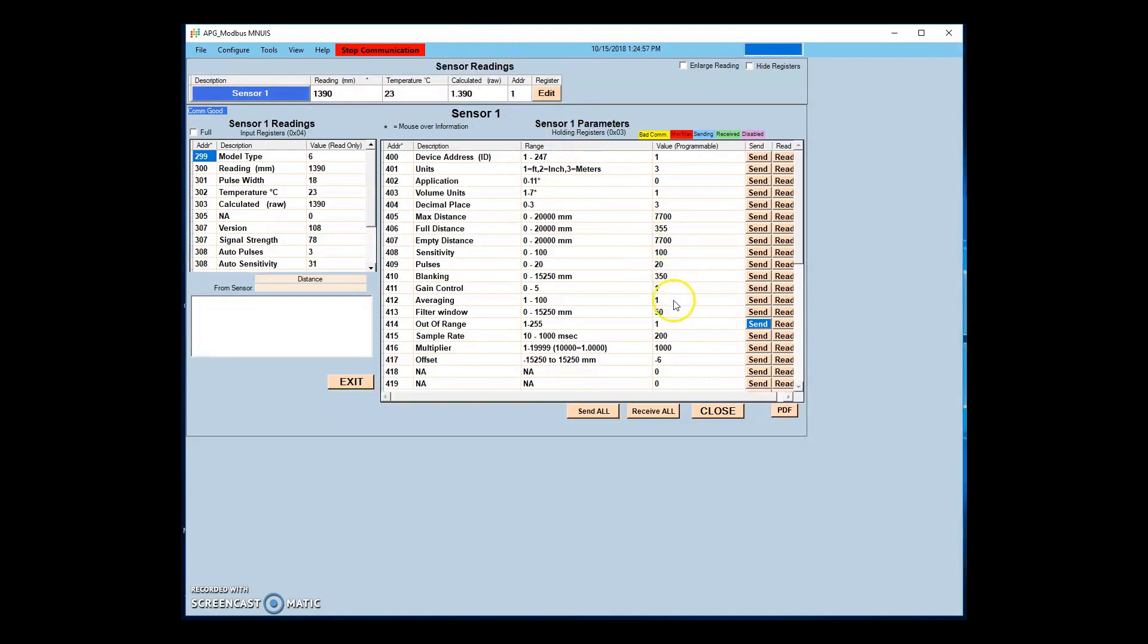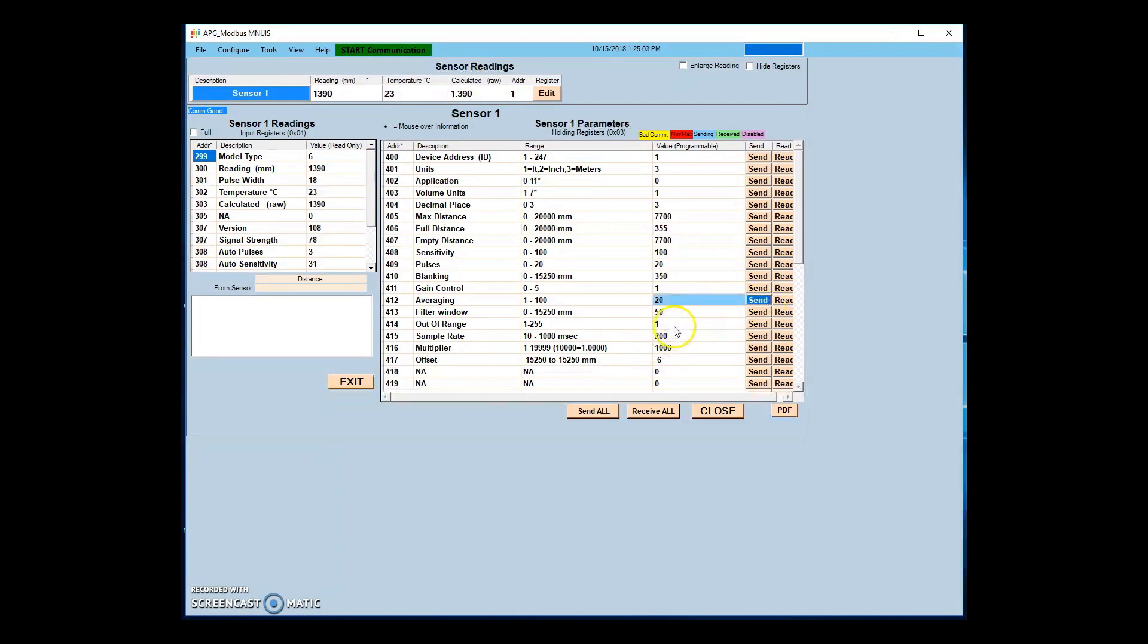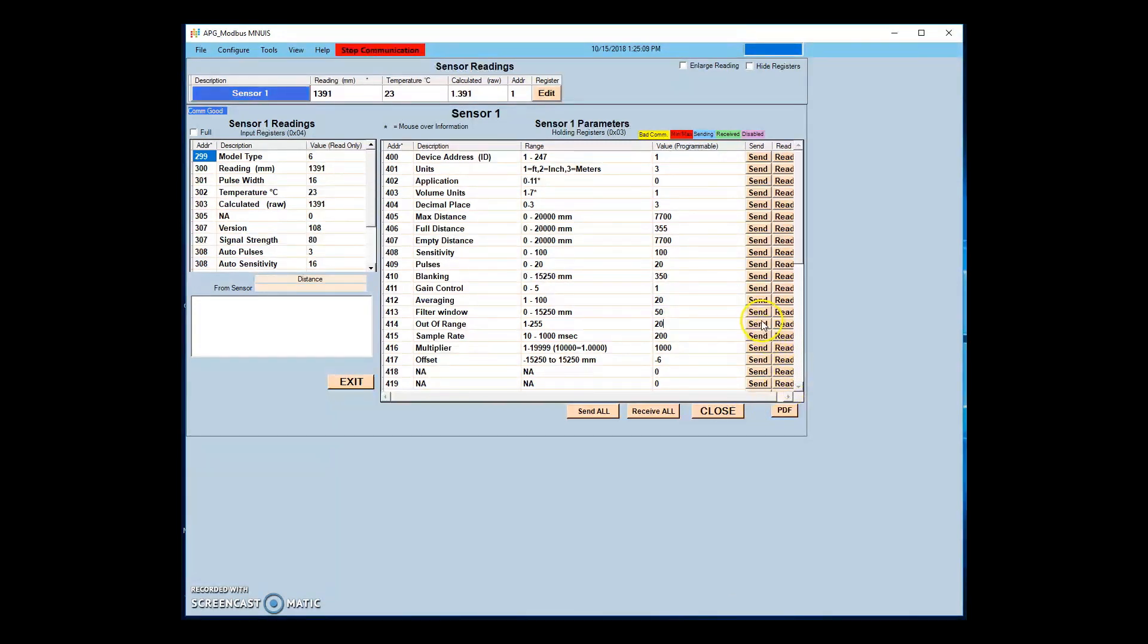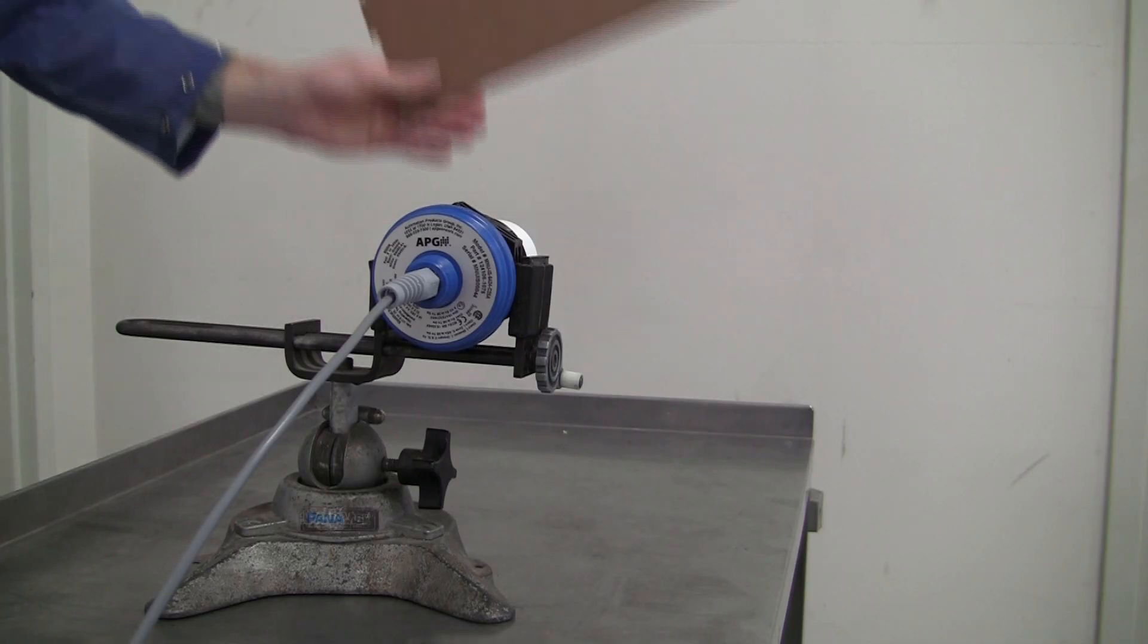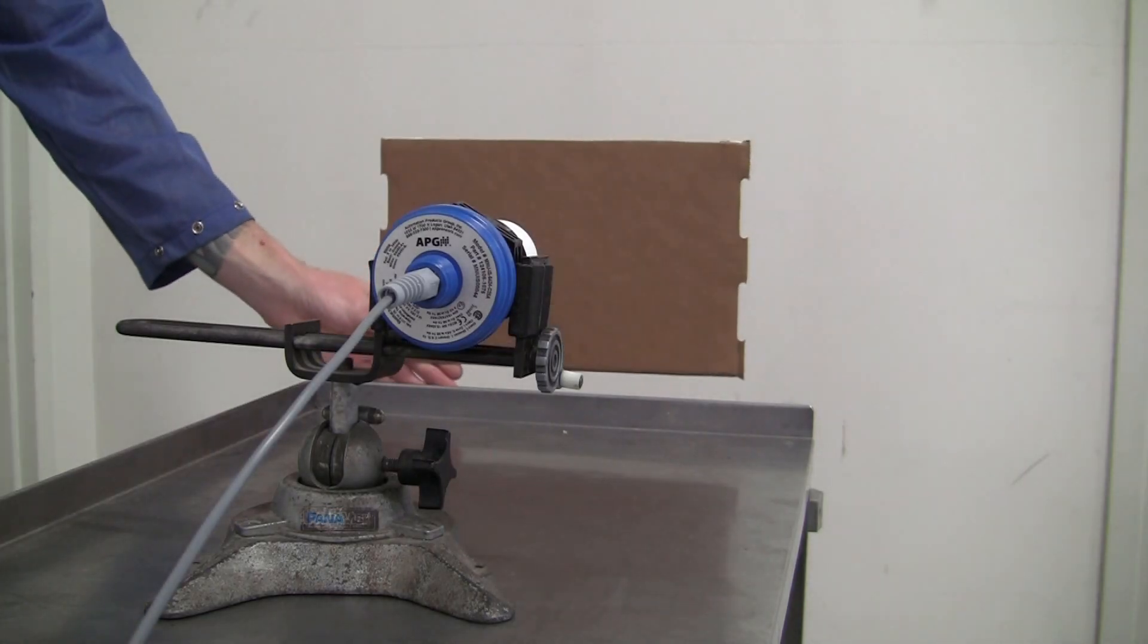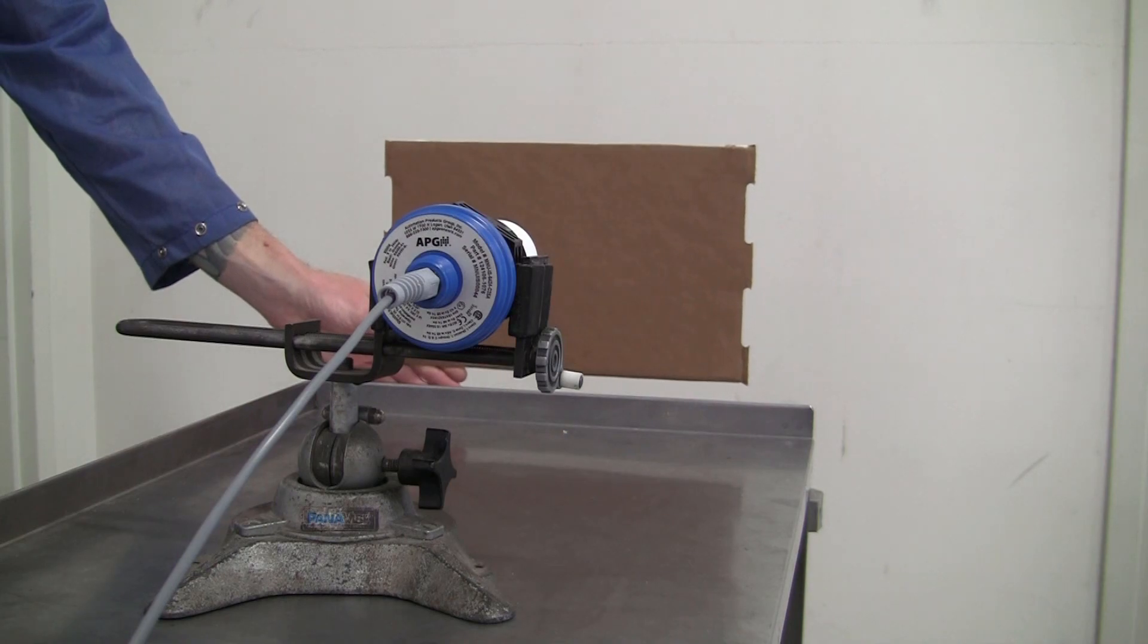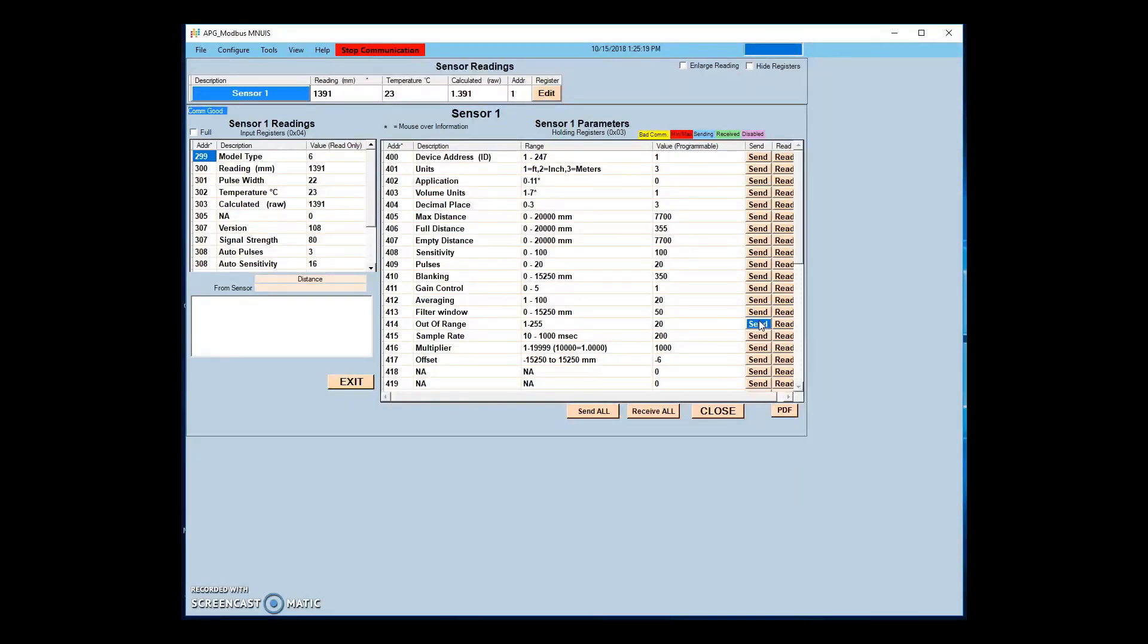Conversely, if we increase the averaging and out of range readings, the sensor will be less prone to catching unwanted targets such as passerbys or waves in a tank application. With averaging and out of range values set to 20, the sensor takes around 5 seconds to respond to the same target. These settings can be adjusted and fine-tuned to the specifics of your sensor environment.